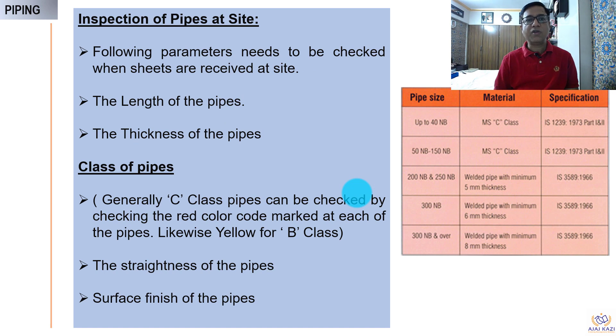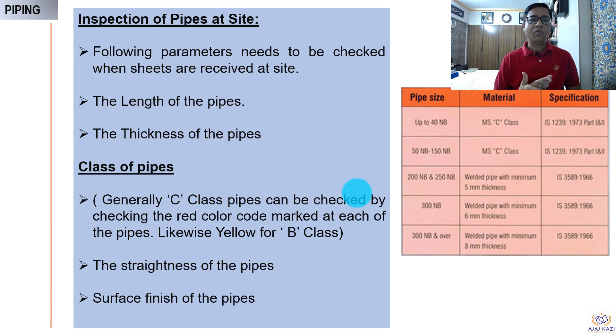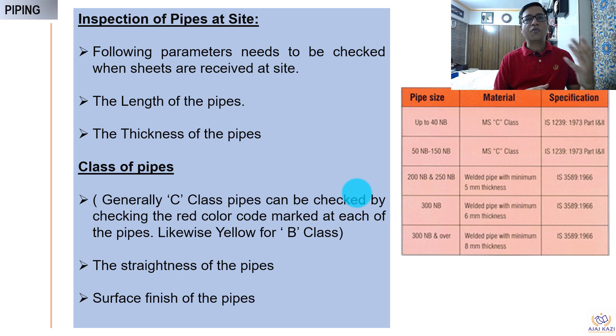When pipes arrive on site, we need to check the thickness and the length. There is a tolerance in the length — it can range from 5.9 meters to 6.1 meters. We also check the class of the pipe based on color code, whether the surface quality is proper, and the straightness of the pipes. There is a table which lists pipe sizes and the related IS standards. In certain projects, seamless pipes are used up to 40 mm diameter, depending on the specification.